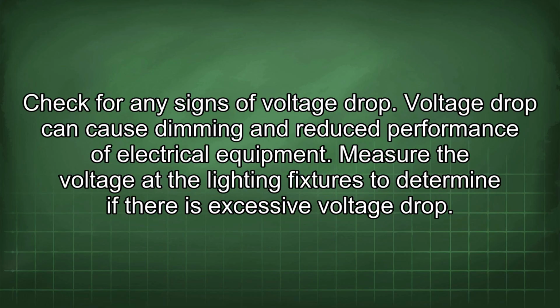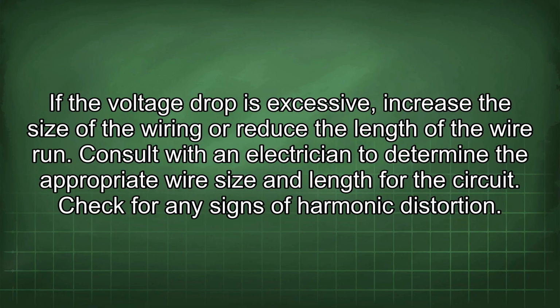Check for any signs of voltage drop. Voltage drop can cause dimming and reduced performance of electrical equipment. Measure the voltage at the lighting fixtures to determine if there is excessive voltage drop. If the voltage drop is excessive, increase the size of the wiring or reduce the length of the wire run. Consult with an electrician to determine the appropriate wire size and length for the circuit.